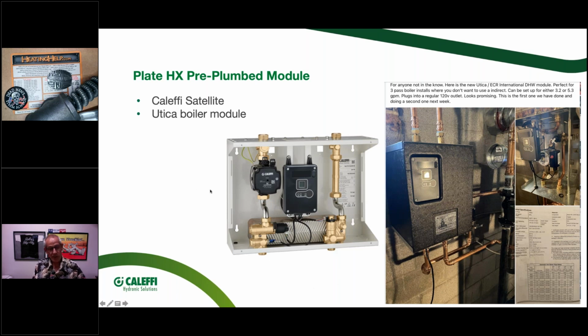And of course, that's going to be based on your incoming water temperature. Some of the projects I visited had big solar thermal arrays that would go into a big storage tank, and then they would have domestic hot water units pulling off these multi-thousand gallon buffer tanks, and that's how they would make the domestic water, with a boiler for backup if they didn't have enough solar stored. I imagine there are other companies making this too - I know some German companies like PAW make a domestic hot water module like that also.